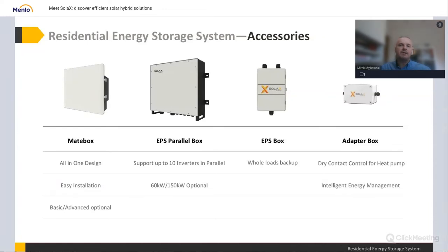If not, if there are only hybrids and batteries with no emergency power, you don't need to buy it. But when you need emergency power connected to your house for multiple hybrid inverters in a parallel system, you have to get the EPS parallel box. The EPS box is just for a single inverter, or maybe two maximum, so it's not as big as the EPS parallel box, but does generally the same for a single inverter if you need to cover the whole house load with emergency power supply.